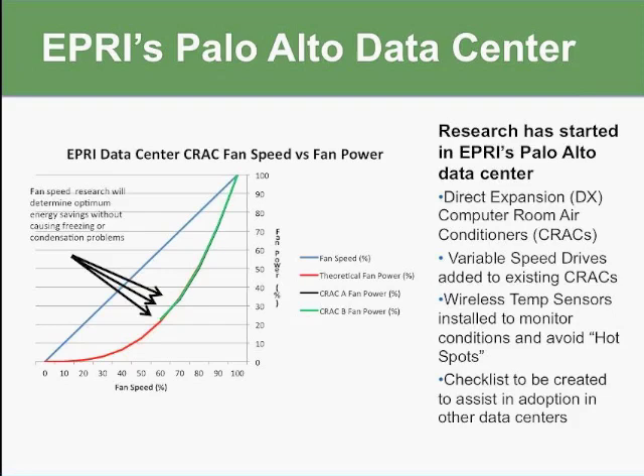The decrease in fan power when you decrease the fan speed is actually the cube of the fan speed. So if you reduce the speed by half, you're actually saving a huge amount of power. We metered the motors, and we indeed got what the theoretical fan curve showed we should. So we're playing around with the Vigilent system, trying to figure out how low to go in reducing the speed of the fans. You want to save energy, but you want to give yourself enough margin that you don't create any hot spots and everything else.